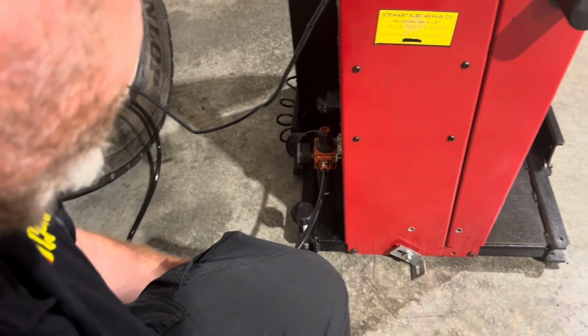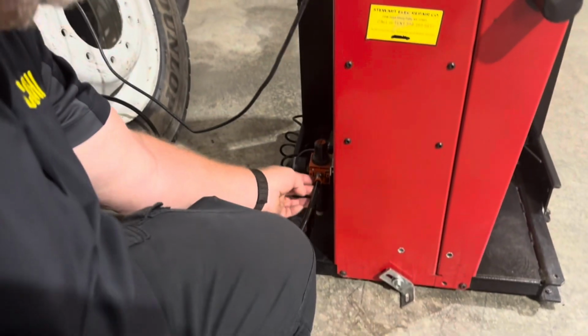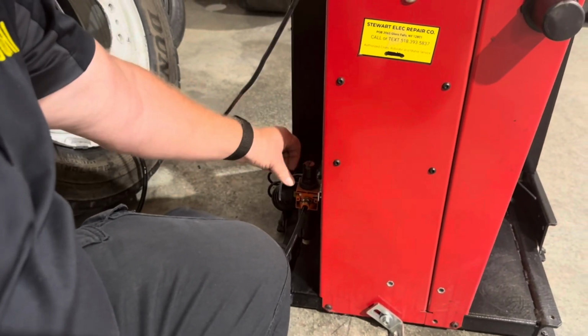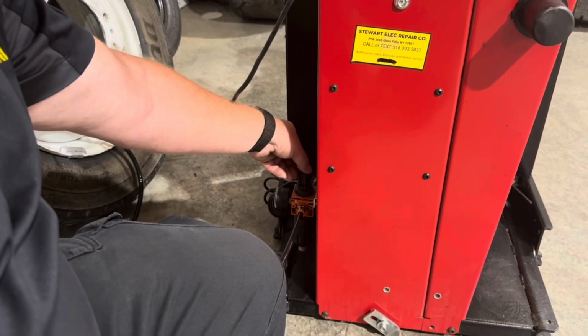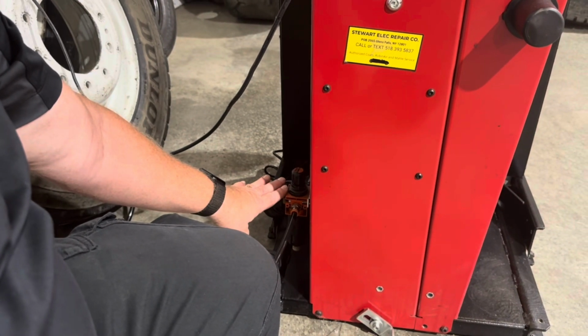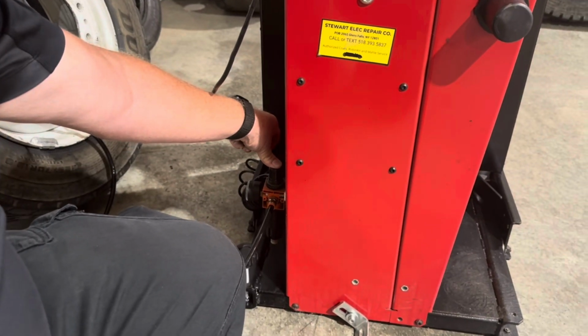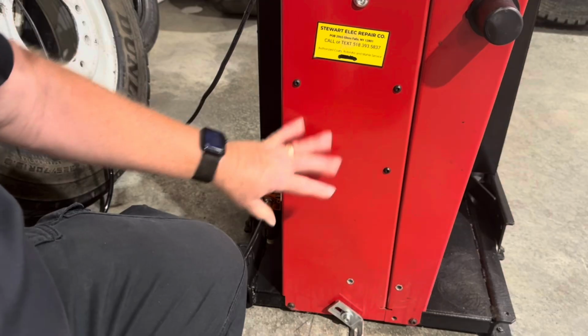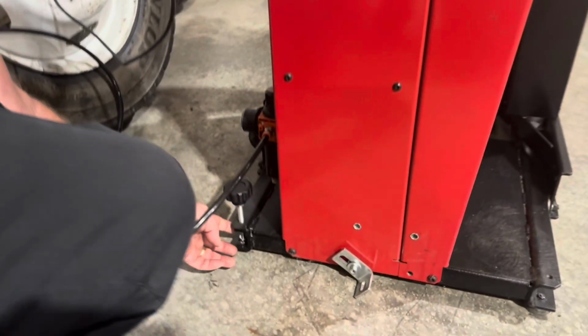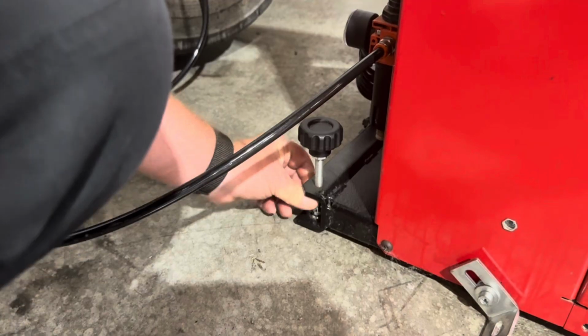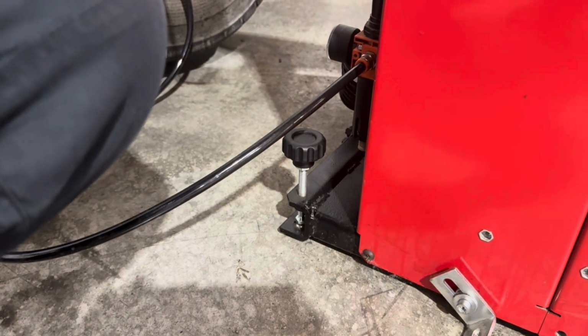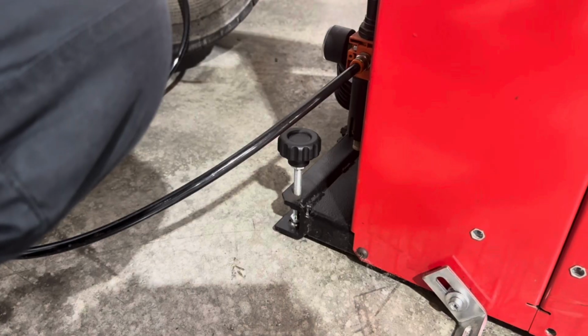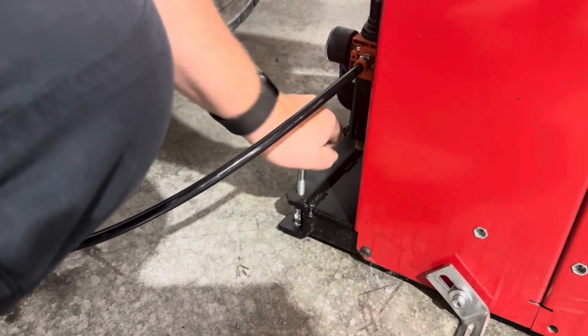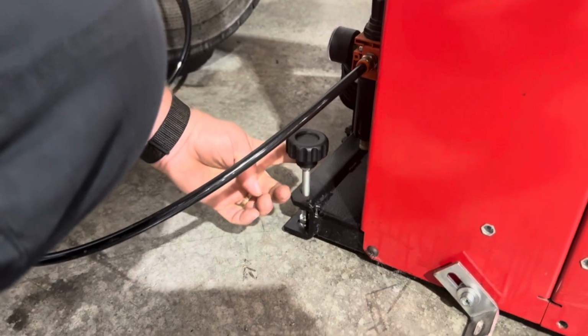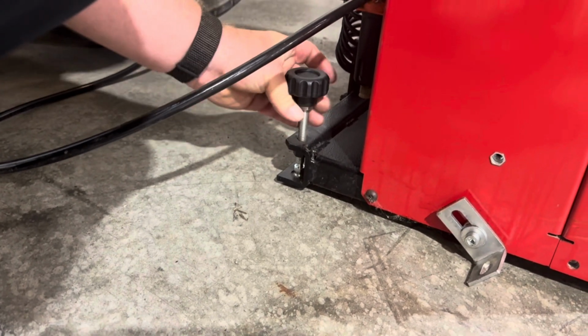Back here is your regulator assembly. You would attach your airline with your fittings that you use. You can pop the regulator up and adjust it to get the maximum pressure. Must be over 120 psi, and then lock that back down. After you have the machine in place, you have a stabilizer leg that's right here, and it has a locking nut on the bottom. You simply want to make sure that the machine is relatively level. It doesn't have to be perfect. And then you would screw this down to stabilize it, and then secure it with the nut up underneath.